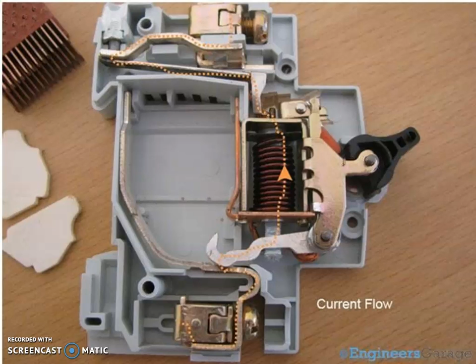This is the connection of the coil, how the coil is connected internally. Now, how current flows through the MCB, meaning how the circuit tripping takes place. Right? During normal operating condition, when the moving contact and the fixed contact are connected to each other, current starts flowing through this fixed contact, moving contact, through this coil, then through this bimetallic strip, and then towards the outgoing terminal.